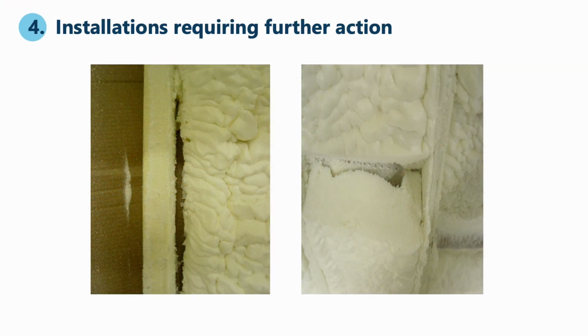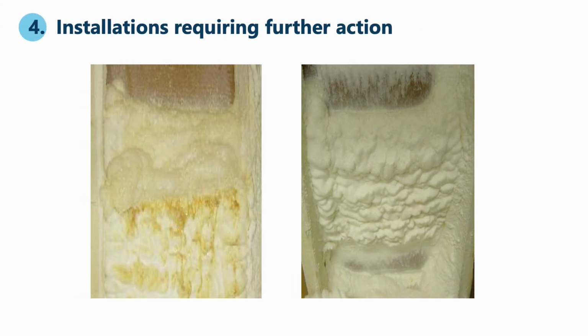In these photos, you will see cracks and gaps in the installation of the spray foam. Whilst these are not perfect, provided all other survey checks are satisfactory, additional spray foam can be added to bring the installation up to the required finish. Other application defects may be encountered, such as uncured product, as shown on the left, or an inadequate amount of spray foam on the right. Again, these can be remediated by the addition of further spray foam.